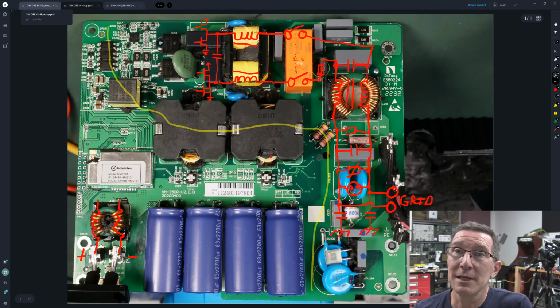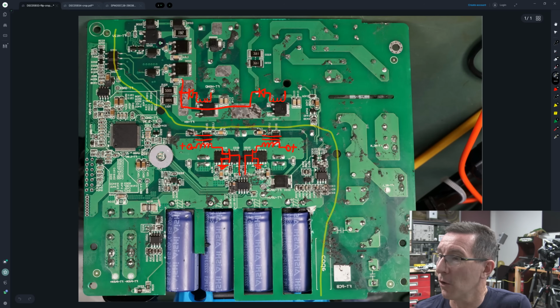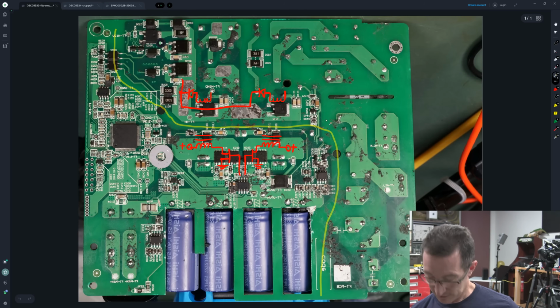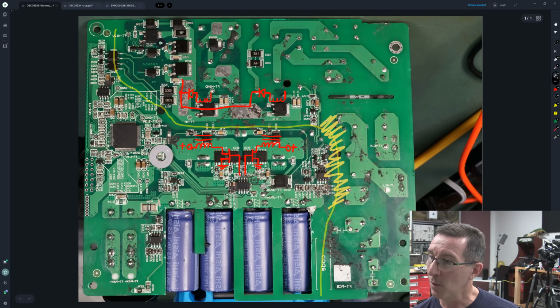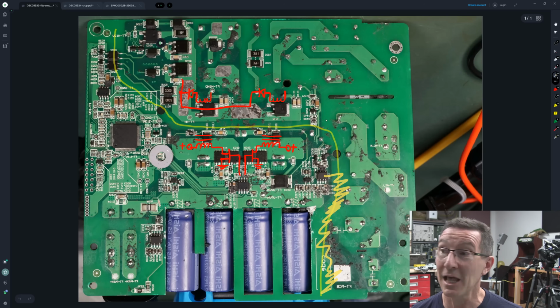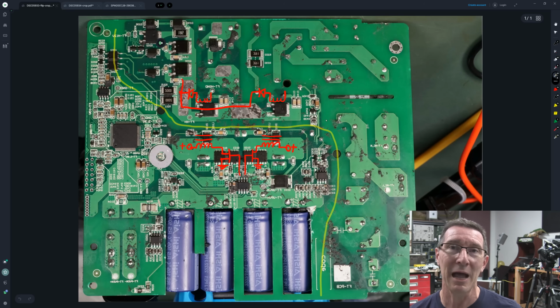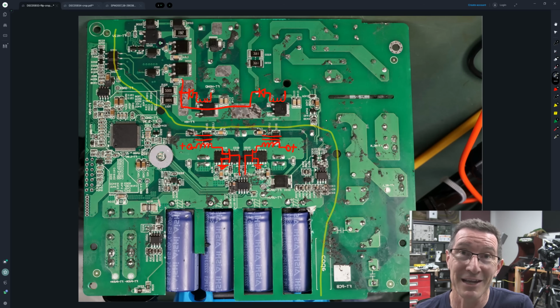Now somebody mentioned the isolation down here, about the creepage isolation, and how that's not really important because we've got galvanic isolation here and there's no need for the current to flow from here to here. Well, not really, because you have to assume the reason the galvanic isolation is there is because you have to assume a fault on the secondary side.